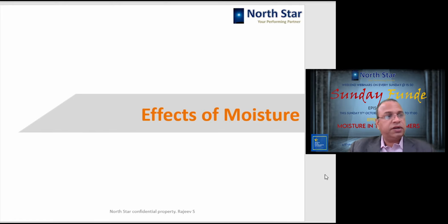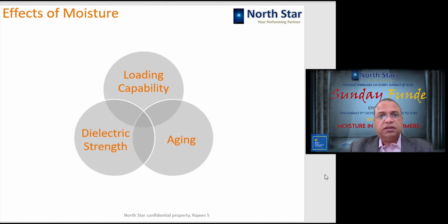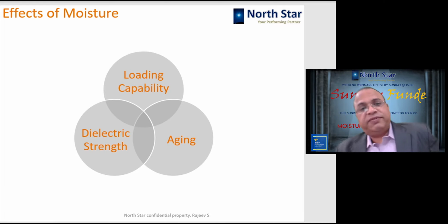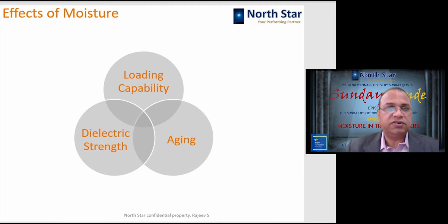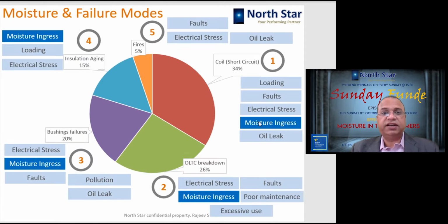Okay, let us look at the effects of moisture. The moisture affects the transformer in three ways. All these three are very critical aspects of a transformer's life, and moisture affects all three of them. It affects loading capability, it affects its dielectric strength, and it affects its rate of aging also.